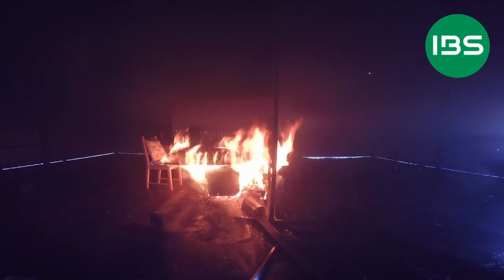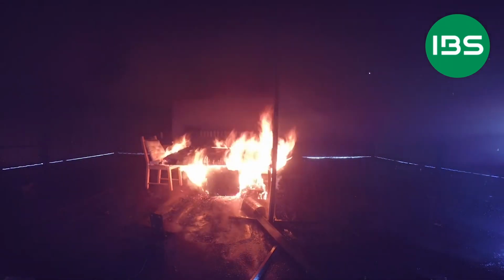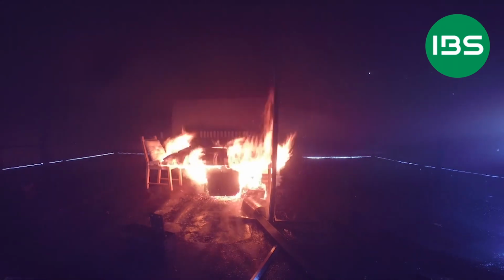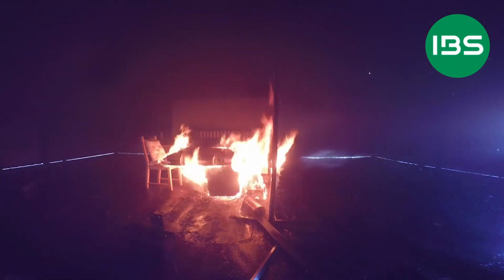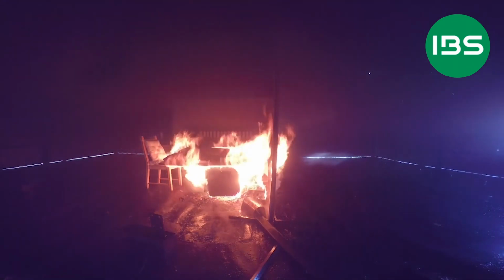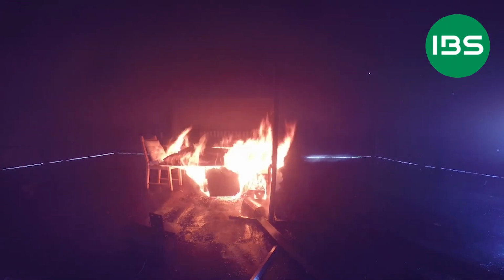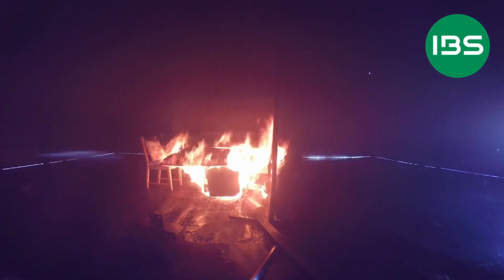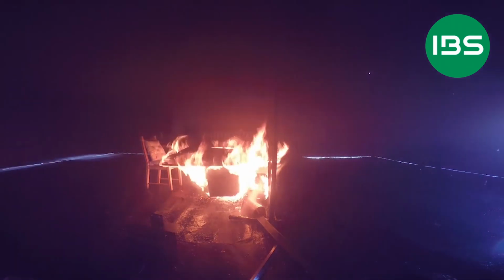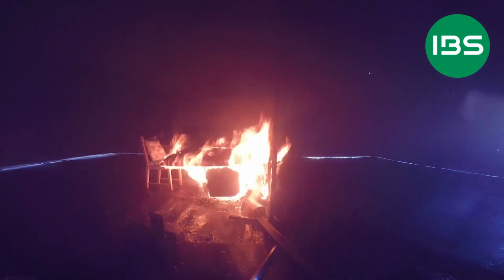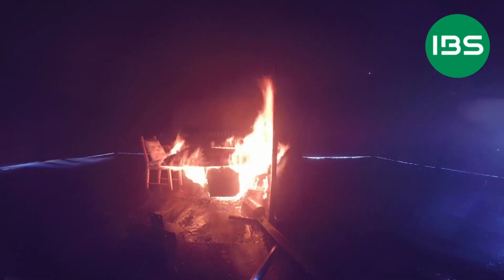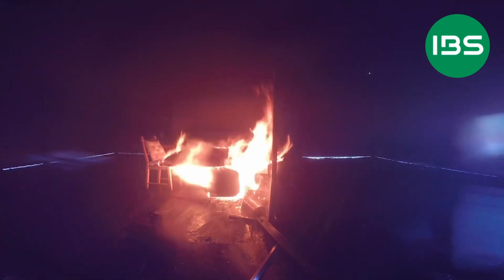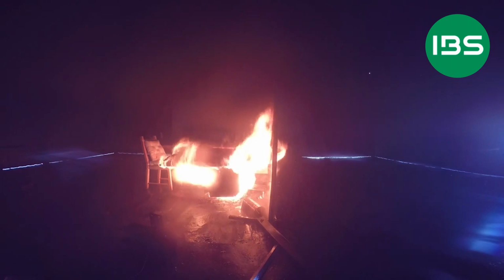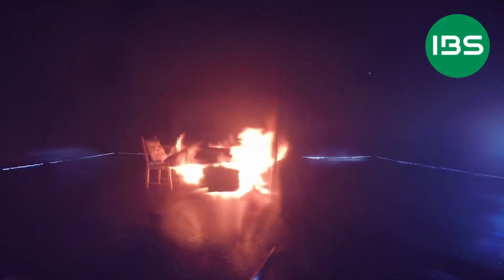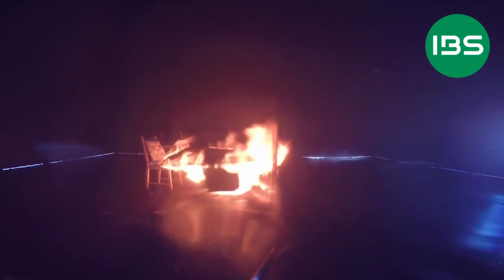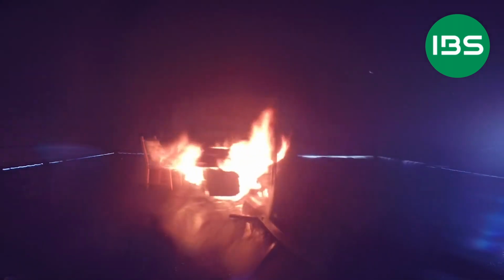What did we have to do? We checked the environmental conditions in advance, but also the test setup itself. Afterwards, the tests had to be done exactly according to the standard specifications. Following each of the tests, we assessed the fire damage and compared it with damage caused by conventional sprinkler systems. After evaluating all available data and documents, we prepared the test report. This was based on the ISO IEC 17025 accreditation standard and EN 14972.